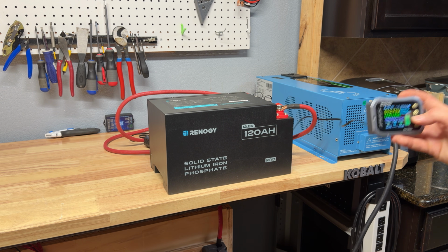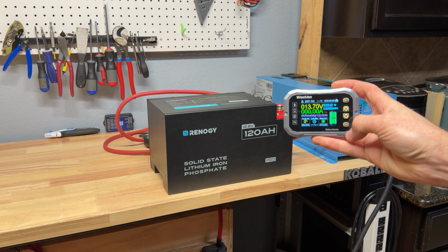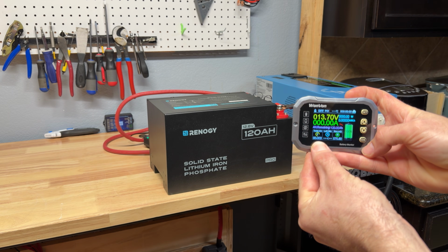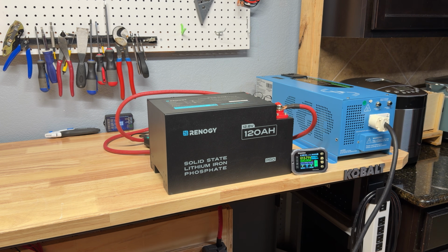All right, we have our current shunt meter here, completely zeroed out and reset. It's going to display the total amp hours we get out of the battery. We're going to do a 0.2C load, so that's 24 amps. I'm going to get our battery charger set up to draw a load from our SunGold Power 3000 watt low frequency pure sine wave inverter, so we'll go ahead and turn the inverter on.